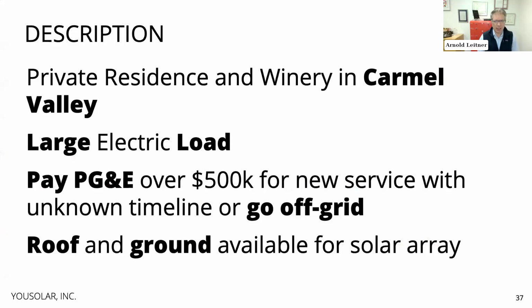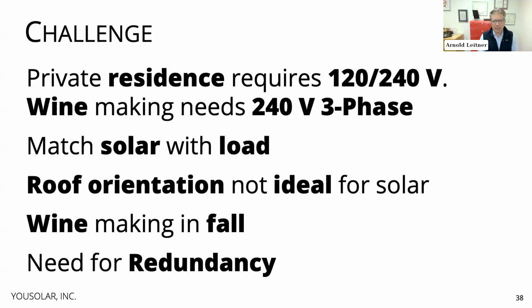It's a private residence in Carmel Valley with winemaking, a large electric load. They would have to pay PG&E over $500,000 for new service with an unknown timeline, so the customer decided to go off grid. We have the roof and plenty of ground available for the solar array, and we took advantage of it. The private residence requires 120/240 volt, but the winemaking requires 240 volt 3-phase, and we had to match the load with solar. We had roofs that were not ideal for solar orientation - that's the least. It's not as beautiful as earlier in Woodland Valley, but the views are spectacular.